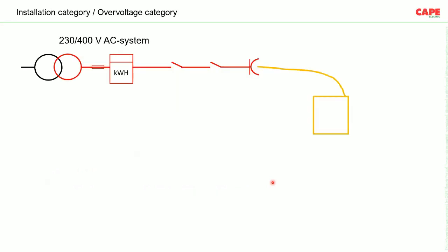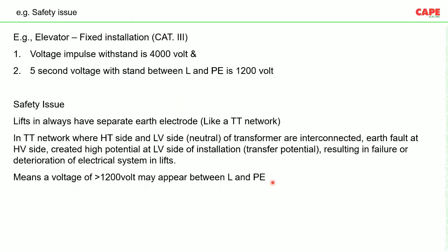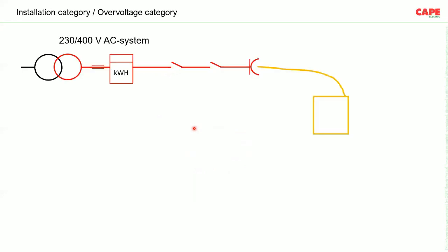If we look at the quality or the life of lift electronics in our buildings, those who are living in high-rise buildings know it. Lift is always a headache. One of the reasons is this: the lift is of category 3. Impulse voltage withstand is 4 kV, but we connect it like a TT and we don't have control over the potential rise during a high voltage earth fault, and we don't take care of it. As a result, a lift may fail.